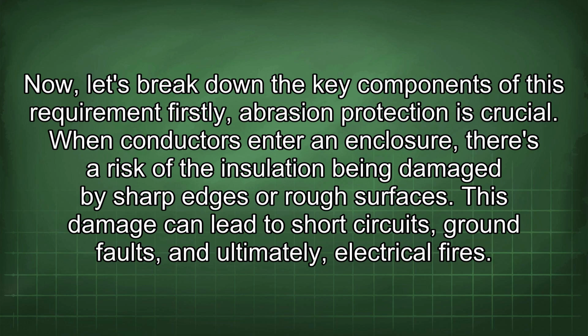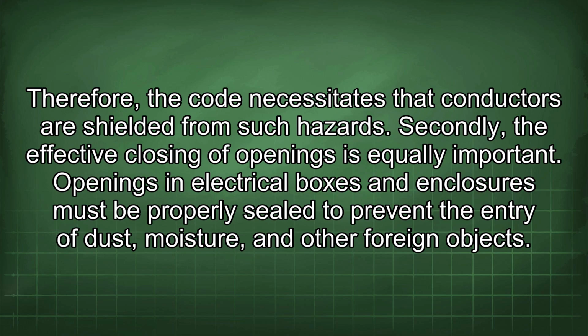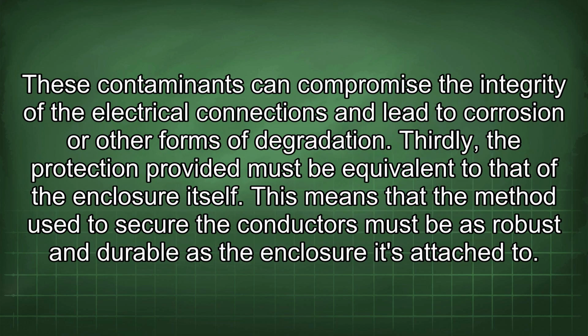Firstly, abrasion protection is crucial. When conductors enter an enclosure, there's a risk of the insulation being damaged by sharp edges or rough surfaces. This damage can lead to short circuits, ground faults, and ultimately, electrical fires. Therefore, the code necessitates that conductors are shielded from such hazards. Secondly, the effective closing of openings is equally important. Openings in electrical boxes and enclosures must be properly sealed to prevent the entry of dust, moisture, and other foreign objects. These contaminants can compromise the integrity of the electrical connections and lead to corrosion or other forms of degradation.